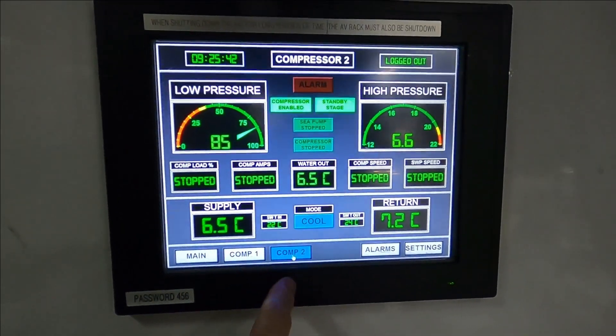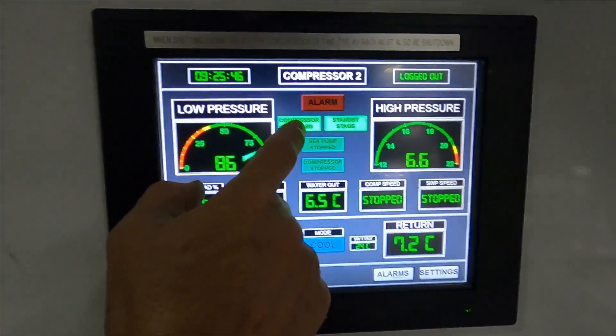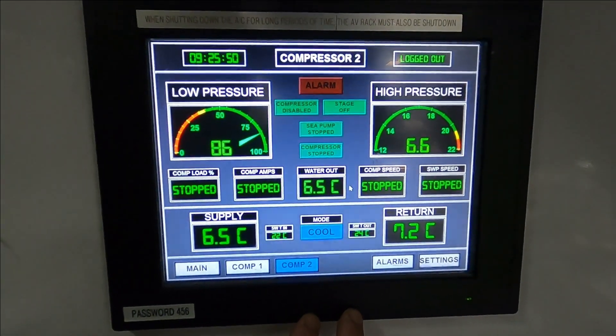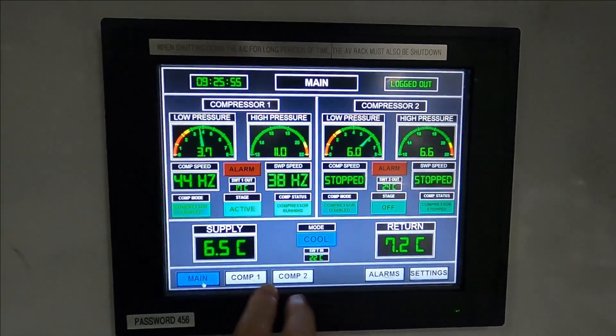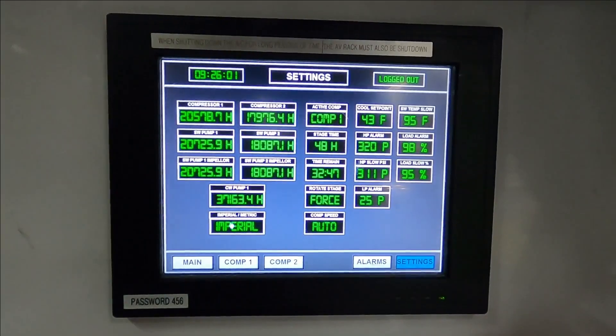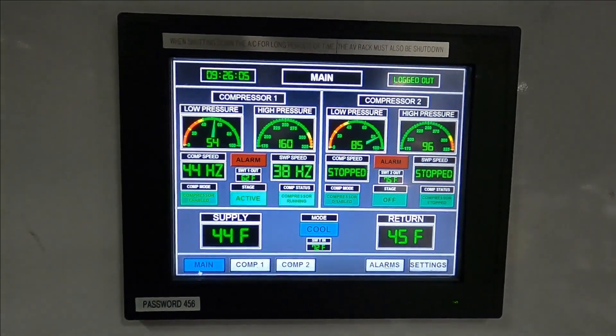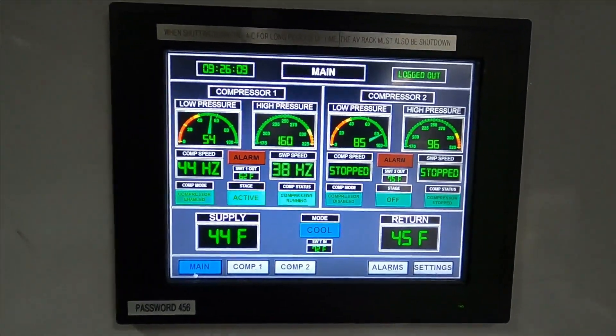They only have one drive and number two is the one that's been shut off. I'm putting 40 hours down for the sea water pumps — I'm giving a full week for that. Number two is now disabled; number one is the active. Now we've got back to Imperial — pressures and Fahrenheit instead of bar and Celsius.